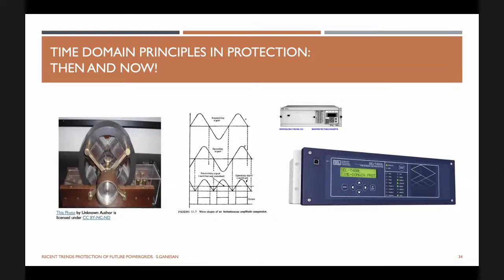They basically check the phase sequence of two signals, whether one signal is leading or lagging the other. The induction motor is a very simple machine in which you reverse the phase sequence - A, B, C instead of A, C, B - and the machine would automatically start running in the opposite direction. So technically it's a very intelligent device wherein, based on the phase sequence, it decides whether to go in one direction or the other. It doesn't have any algorithm, it doesn't have any mathematics inside, but it's basic fundamental physics behind the induction principle which helped us do that.